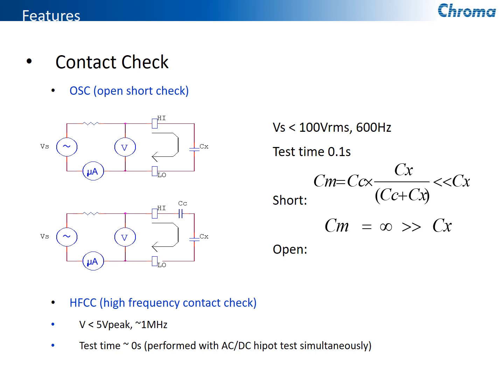This probably should have been at the beginning of the presentation. This is what we refer to as a contact check, and we refer to it as a high frequency contact check.